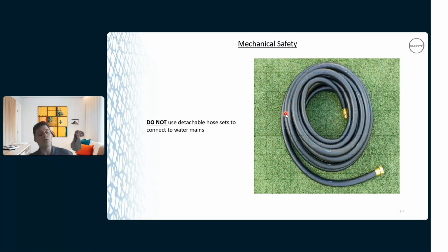So yeah, that's the correct way to deal with that. Don't use detachable hoses - we're looking for rigid pipework connecting into the heat batteries. People might be tempted to use flexible hoses or plastic, but we're looking for rigid copper pipe to go into it. From your isolation valve, you should convert that to copper to the heat battery circuit, as I call it. When coming out of the TMV, you can convert to plastic or whatever if you want, but you have to have rigid copper going into the battery, okay?